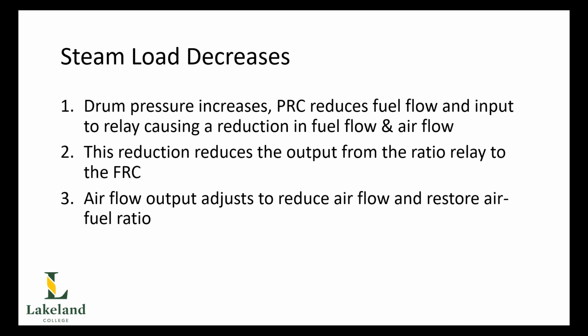All right, well, what about if there's a steam load decrease? Just reverse it. When steam load decreases, drum pressure is going to increase. When the drum pressure increases, the pressure transmitter is going to sense that and output its value into the pressure recording controller. The pressure recording controller now is going to generate a signal out to reduce the fuel flow and reduce the airflow.